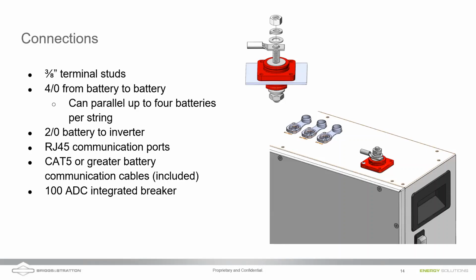If you're doing that, make sure to use 4/0 cable with some really solid crimps. I would recommend just pre-ordering a cable that's a set length that you know it's going to be. 4/0 can be a little difficult to crimp. And using 2/0 from one of the batteries to the inverter. So this goes for up to 4 batteries. If you're over 4 batteries, we'll discuss different wiring methods required there.